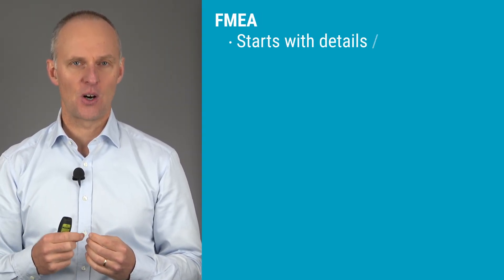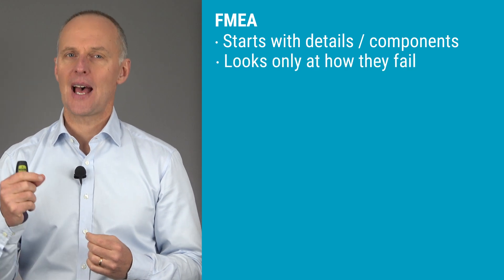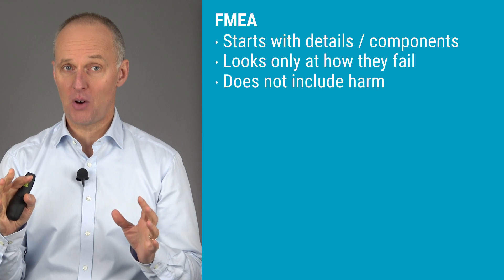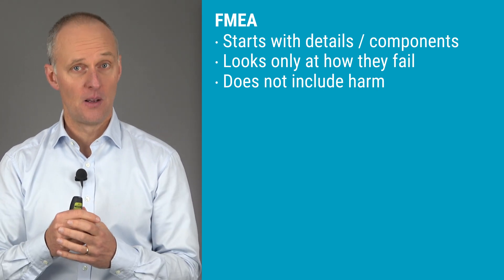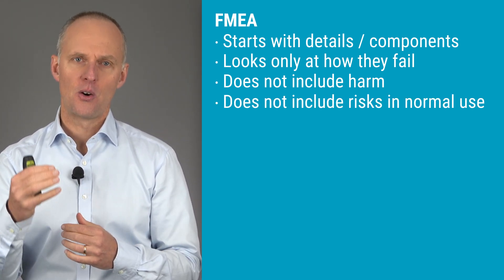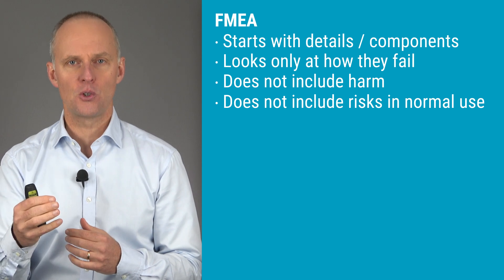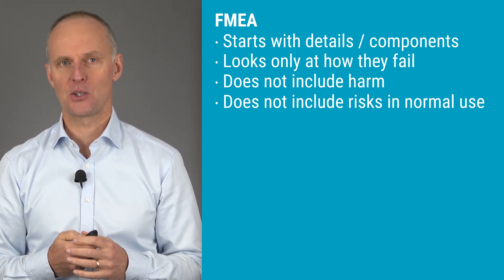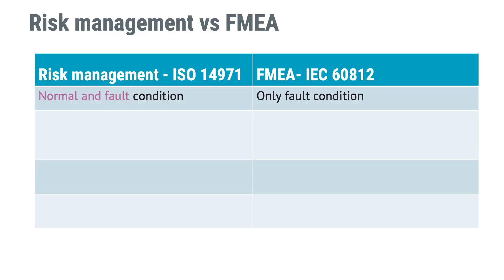Having looked at these examples, you may have noticed that FMEA starts with details or components. You would be looking at how specific components or process steps could fail, and there was no mention of harm in these FMEAs. Since we've only looked at failure risks, risks relating to normal use have not been included. Risk management according to ISO 14971, on the other hand, includes risks both from normal use, reasonably foreseeable misuse, and fault conditions — whereas FMEA only looks at risks relating to failure.